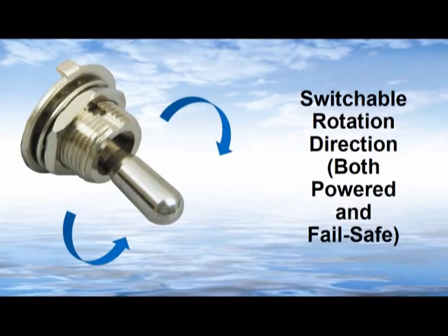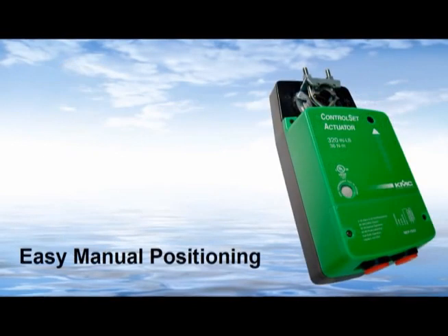Not only can a capacitor-driven fail-safe easily change directions, it might also be turned off if desired, such as for testing purposes. The easier installation of capacitor-driven actuators is further enhanced by a quick-release button or lever that allows easy manual positioning of the shaft.